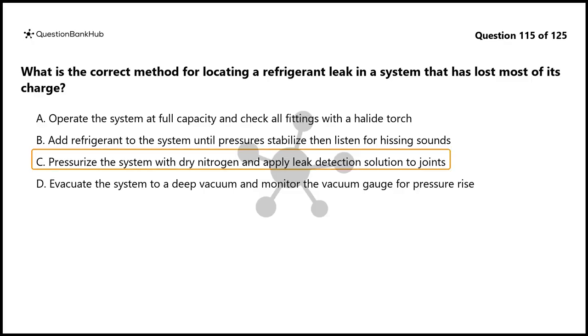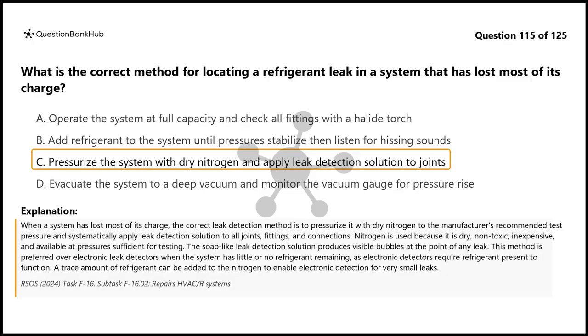The correct answer is C. When a system has lost most of its charge, the correct leak detection method is to pressurize it with dry nitrogen to the manufacturer's recommended test pressure and systematically apply leak detection solution to all joints, fittings, and connections. Nitrogen is used because it is dry, non-toxic, inexpensive, and available at pressures sufficient for testing. The soap-like leak detection solution produces visible bubbles at the point of any leak. This method is preferred over electronic leak detectors when the system has little or no refrigerant remaining, as electronic detectors require refrigerant present to function. A trace amount of refrigerant can be added to the nitrogen to enable electronic detection for very small leaks.